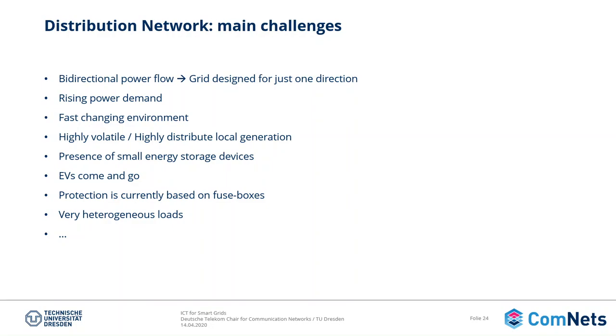Therefore, it might actually be very dangerous for the distribution network if these fuse boxes cannot detect short circuit currents anymore, so they don't detect faults in the network because of this change in power flow. You need more intelligent ways to detect a fault, based on monitoring the individual power lines, not measuring it based on the traditional fuse box threshold current way.